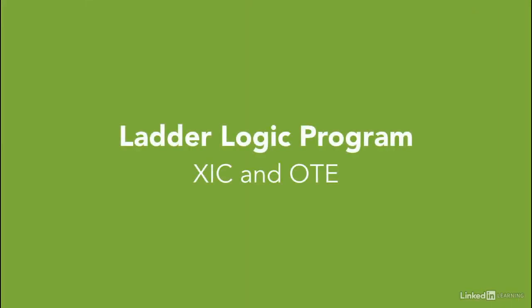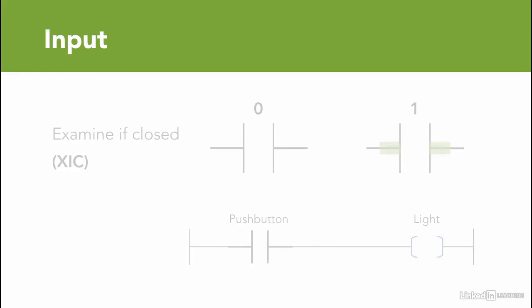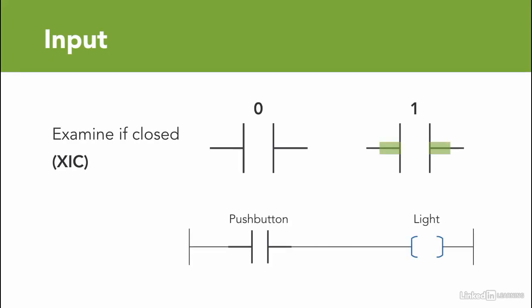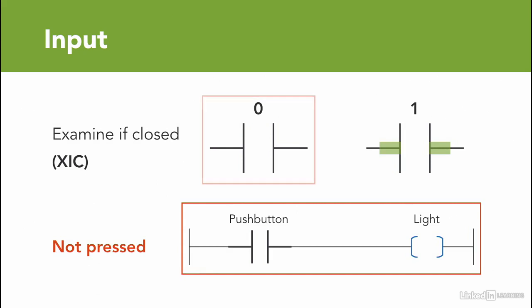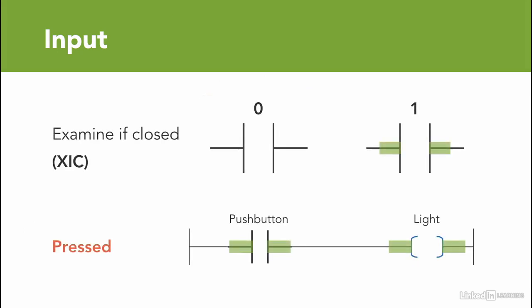Let's see how the Ladder Logic program behaves when using the Examine If Closed instruction. Using XIC instruction, the instruction is only activated when the memory location is 1. So when the push button is not pressed, the logic state is 0, the instruction is false, and the light will not turn on. When the push button is pressed, meaning the logic state is now true, equals to 1, then the instruction is highlighted and, according to the continuity, the light will turn on.